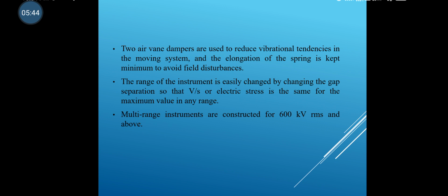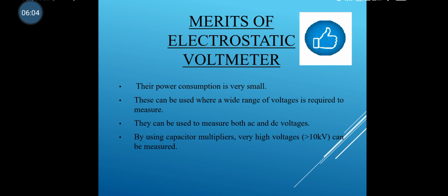The range of the instrument is easily changed by changing the gap separation so that V by S, or electric stress, is the same for the maximum value in any range. Multi-range instruments are constructed for 600 kV RMS and above. As every system has some advantages and drawbacks, these electrostatic voltmeters also have some advantages. That is, electrostatic voltmeters have low power consumption. They are used where a wide range of voltages needs to be measured. They are used to measure both AC voltage and DC voltage. By using a capacitor multiplier, very high voltage greater than 10 kV can be measured.